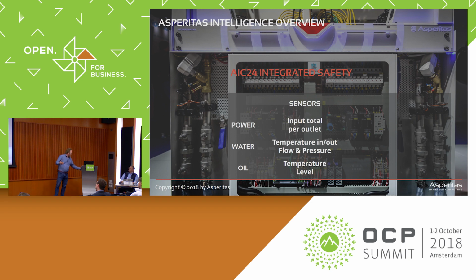All that information is combined with a level of control. Even though we don't need to apply regulation on the internal thermodynamics, we do apply control for safety purposes - there are relays controlling the power input to the immersion system, and electric valves to manipulate the flow rate of water going into the convection drives.